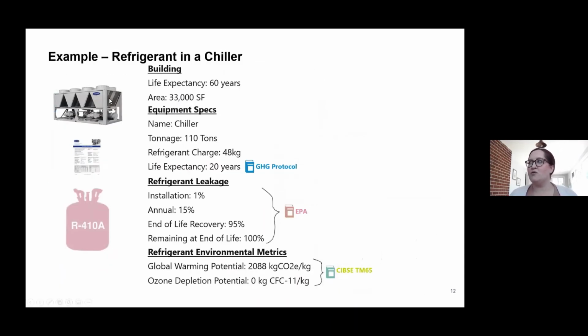So if we go through just a simple example of something like a chiller. You'd expect that your building's going to last about 60 years, let's say it's 33,000 square feet. You'd have your equipment specifications here of it being a chiller, which is pretty centralized, not a ton of leakage comparative to something like a VRF system. Let's say it's 110 tons. The refrigerant charge would be about 50 kilograms, and the life expectancy for that chiller is 20 years.